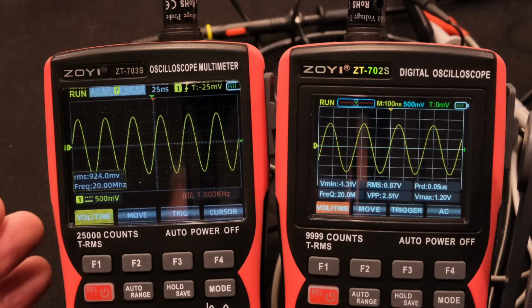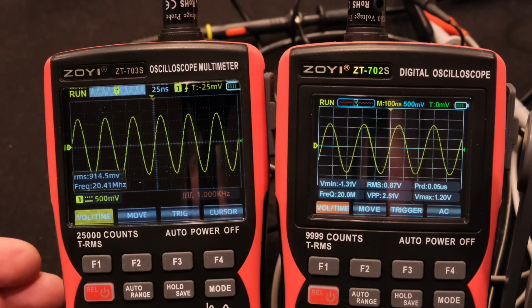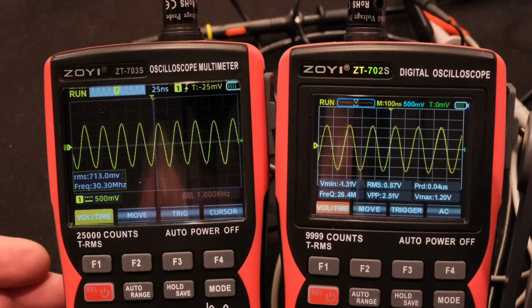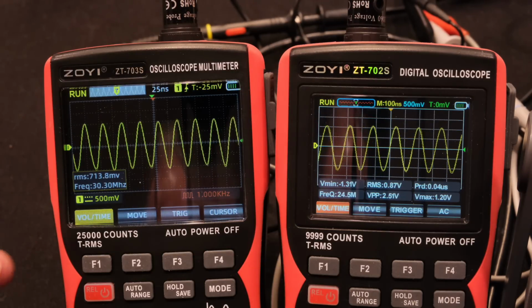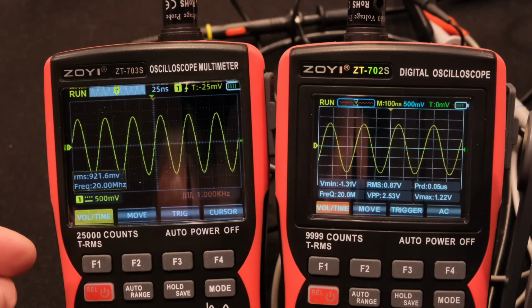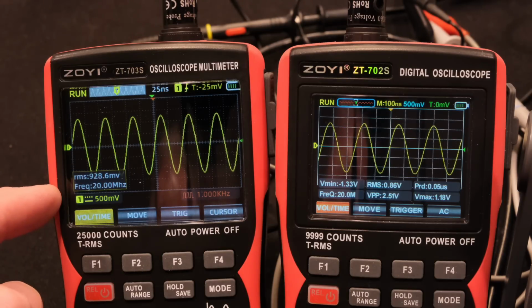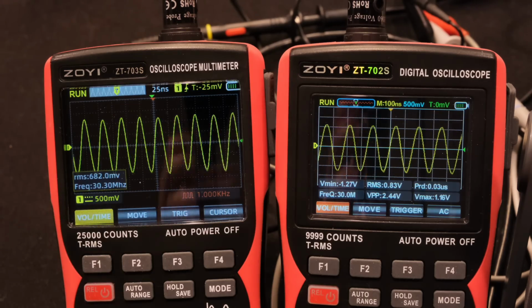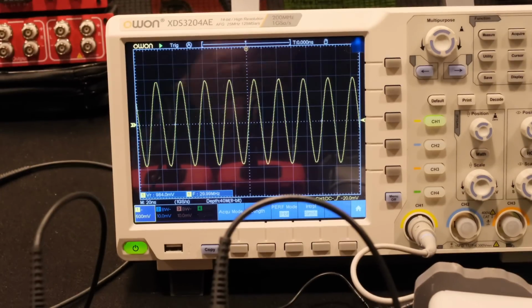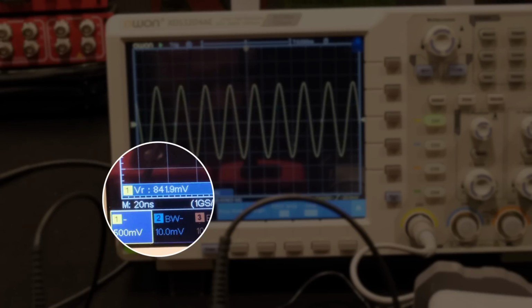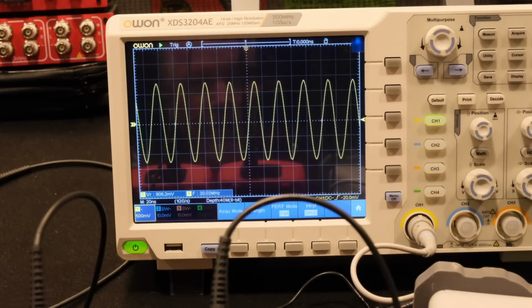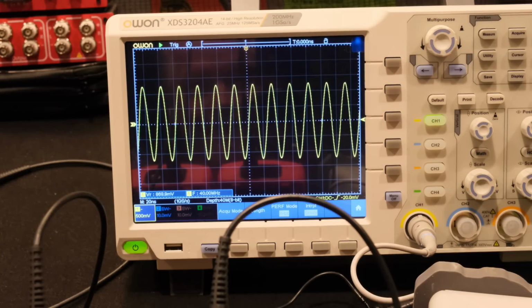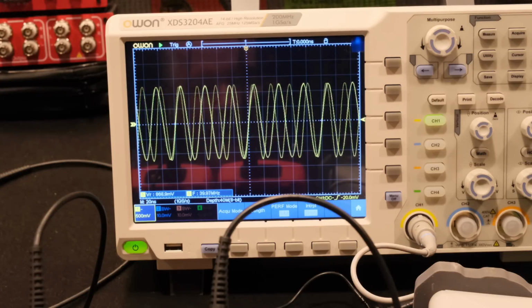Okay, now it's pretty happy at 20 meg. Okay, let's go to 30. Now it's dropping in amplitude, but I think it's about 790 millivolts. And right there, it's about 928, so it's already dropped a little bit. So the scope is starting to drop down, because when I look up here at the Owon, it is right now 960, but if I go back down to 20, it's 1 volt. So the generator's also dropping. I think this is supposed to be an 80 meg generator, but at 30 meg, it's already starting to drop out. So okay, 40, it didn't drop very much more, right?